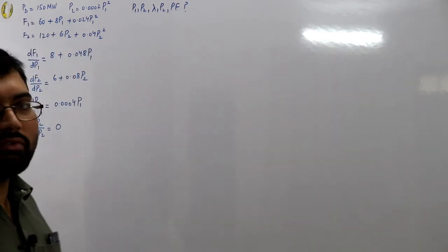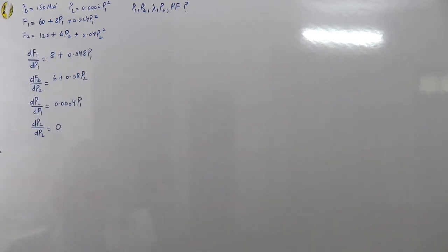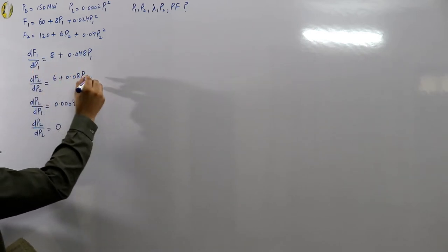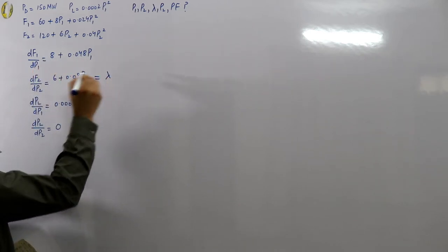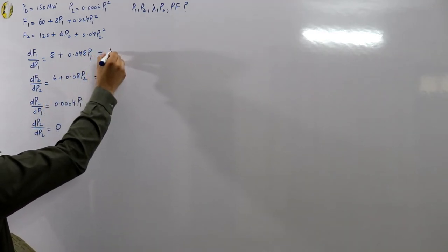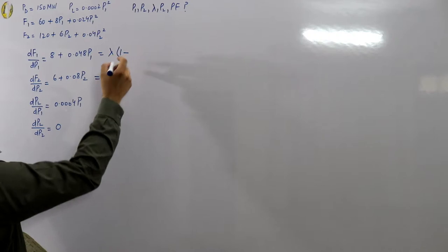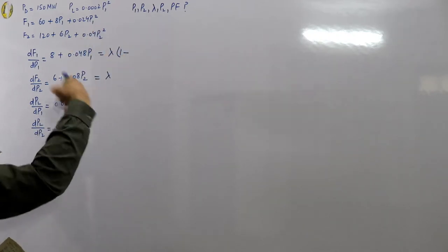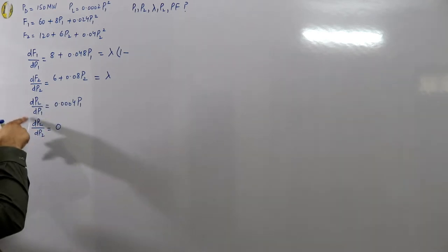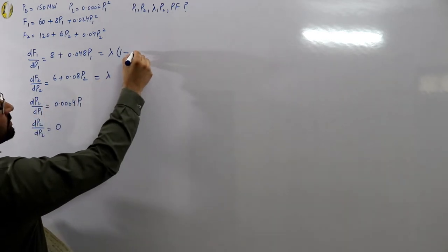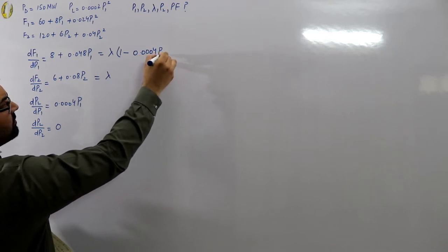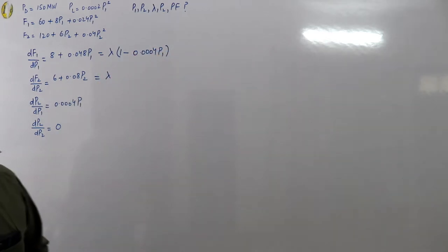If there is no power loss associated with a station, the derivative equation directly equals the incremental cost lambda. Whereas if losses are associated, the condition is dF/dP = lambda × (1 − dPL/dP). For station 1, this gives: 8 + 0.048 P1 = lambda × (1 − 0.0004 P1).